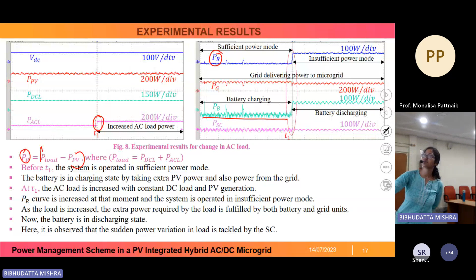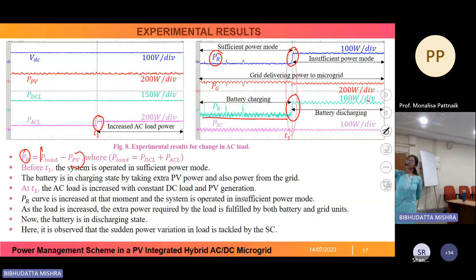Then at T1 point, we increase the AC load power. As we increase the AC load power at this point, the PR value becomes positive. Previously the PR value is negative, and at T1 it becomes positive, meaning previously it was working in sufficient power mode, and after T1 it is working in insufficient power mode. To compensate and provide that extra amount of load power, the battery, previously in charging condition, now comes to discharging condition. Here we can see the transition from charging to discharging condition.